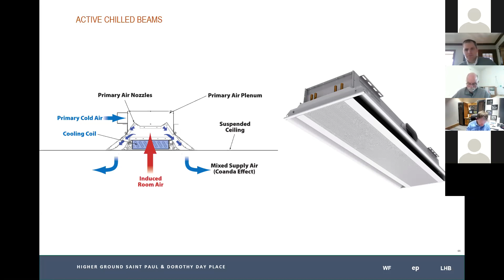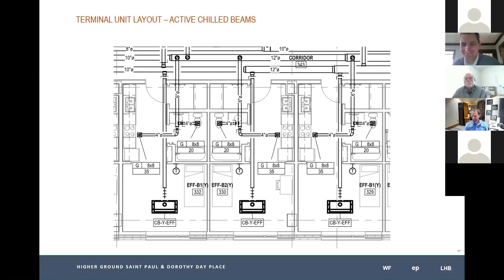You can go to the next slide. Here's the layout. I shared the layout in Higher Ground. Here are our 3 efficiency units. And we have a chilled beam for every unit. We have outside air and exhaust directly ducted to each of the units. And the anecdotal evidence is that Dorothy Day has fared better than Higher Ground in terms of COVID. And you can kind of see why. So it looks like we predicted COVID in this case. We didn't, but this is the approach we took. And then I pointed out in Higher Ground how it would have been better to have units closer to where they were serving. In this case, we did that. We scattered these air handling units closer to where they're serving.